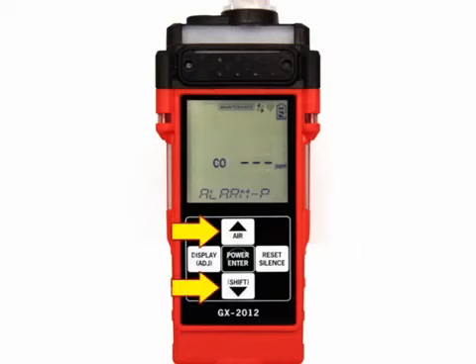Use the air or shift buttons to select the CO channel and press power enter to display the warning setting. Adjust the values for the warning and alarm settings using the procedure just explained. When you press power enter after selecting the alarm value, you will then be prompted to select the STEL value. Use the air or shift buttons to change the setting and press power enter when finished to save the setting. You will then be asked to enter a TWA value. Use the air or shift buttons to change the setting and press Power Enter when finished to save the setting and return to the alarm point screen.